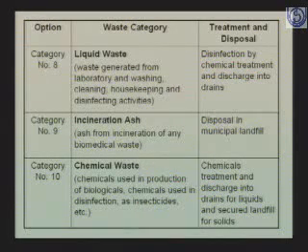The next category is liquid waste, and we know that this is the waste from laboratories, the blood bank, and operation theatres. Liquid waste management, in fact, has been a very weak link all over, especially in this country. We have corporate hospitals and 5-star hospitals, and they will have good facilities for the waste management of the other categories, but when it comes to liquid waste management, you will rarely find even the best of hospitals having effluent treatment plants.